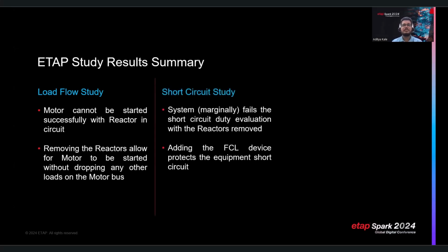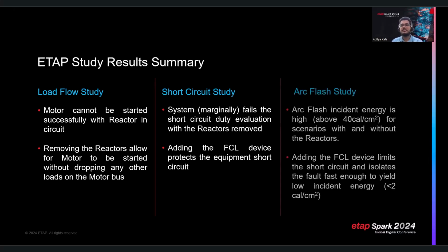Then we looked at the short circuit study where the system marginally fails because of the high short circuit duty when the reactors are removed. Adding the fault current limiter device protects the system from this high short circuit current. We then looked at the arc flash study. The incident energy was above 40 calories per centimeter square for scenarios with and without the reactor. However, adding the FCL has not only limited the short circuit current, but it's also isolating the fault fast enough to yield a very low incident energy result, which is less than 2 calories per centimeter square.